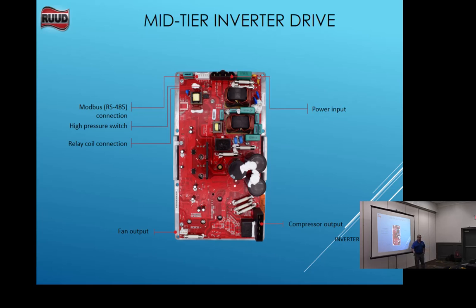Brand new out of the box inverter fault. They happened to notice when it started to run, they saw a little arc. Well, those fuses were just a little bit too close together. So they turned the power off, let it de-energize, took a screwdriver and just kind of bent them over just to get a little bit further apart, fired up and ran fine. So just in case you have that, just look in that area and make sure that they're not touching. Probably just what got pushed on the board and it didn't get in the right spot exactly.